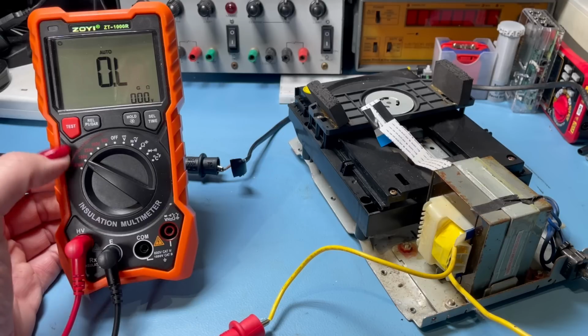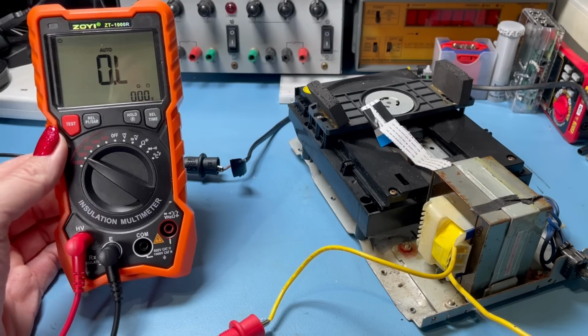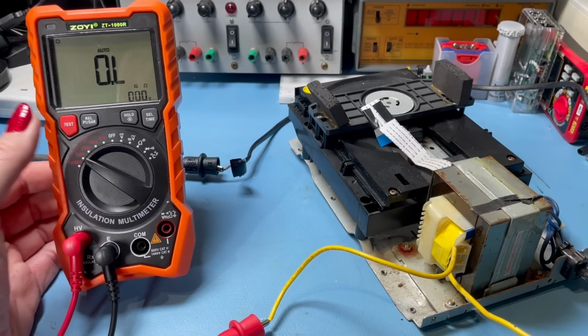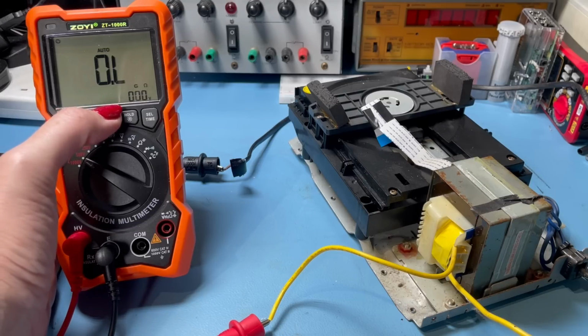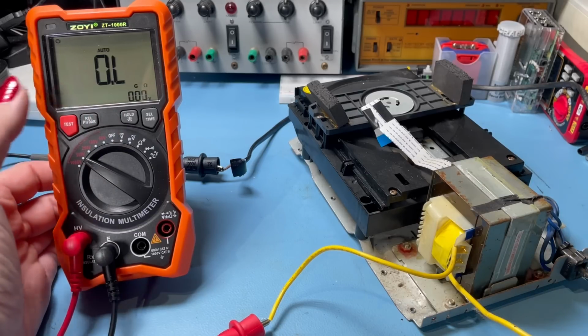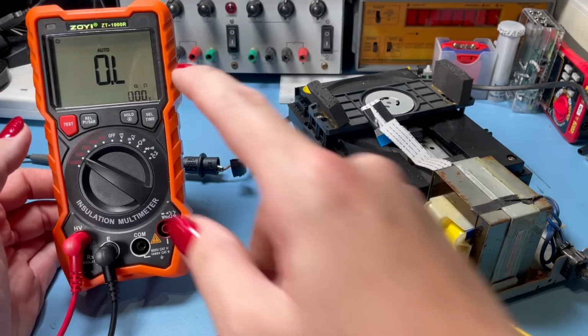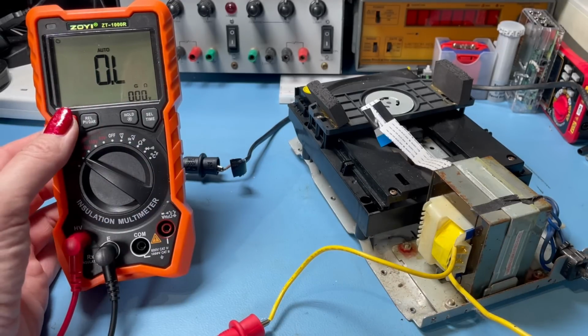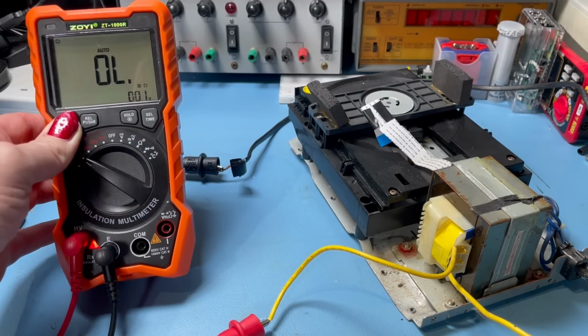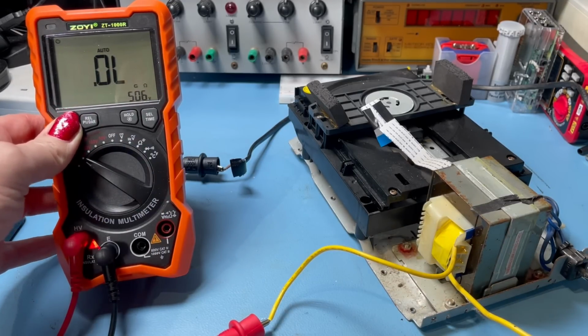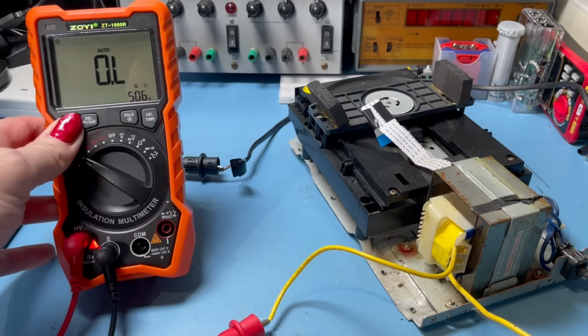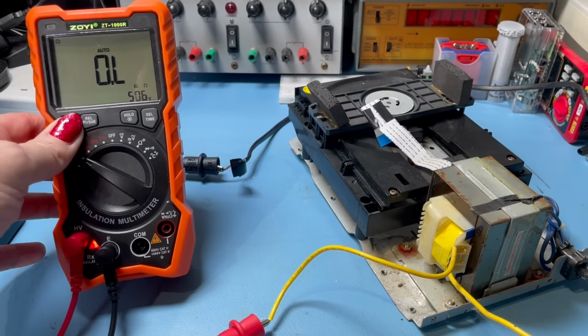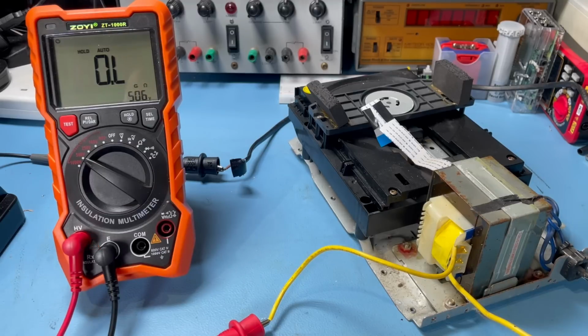So what we'll do, initially, we'll just give it an insulation test. Now, this measures insulation resistance up to 20 gigohms. So if the insulation of the transformer is more than 20 gigohms, it will just show as overload. So let's hold down the test button. Warning triangle, it's putting out 506 volts, just getting a reading of overload. So we know the insulation of this transformer is better than 20 gigohms. So it's a good transformer.